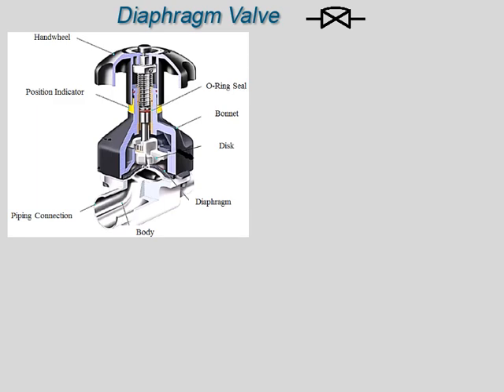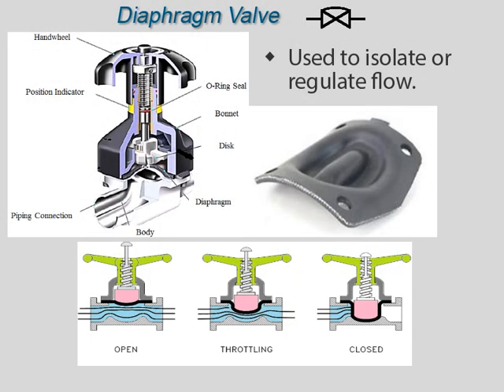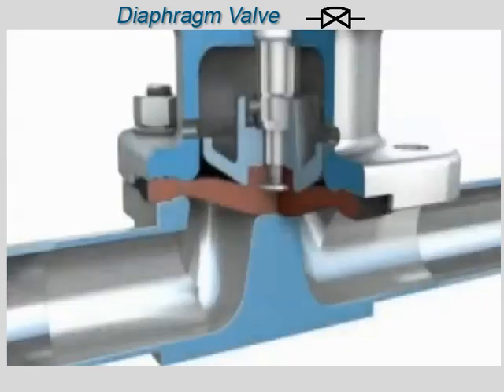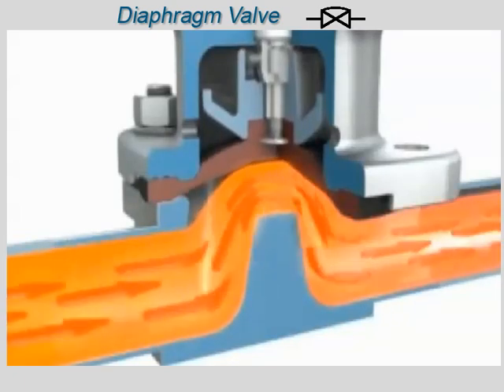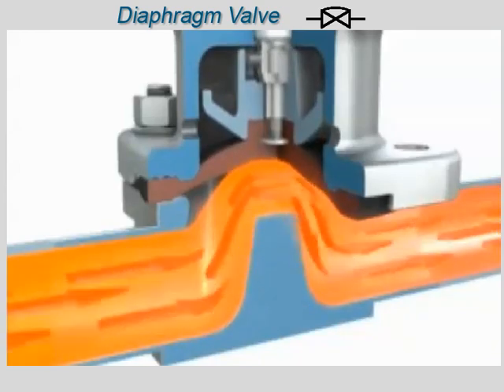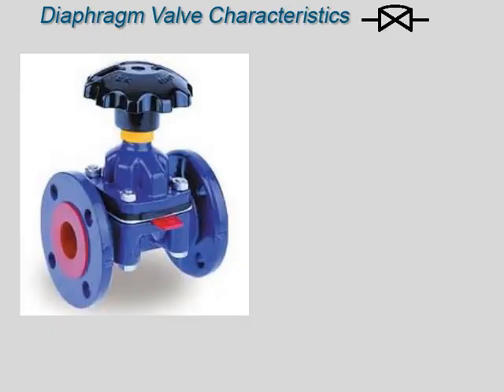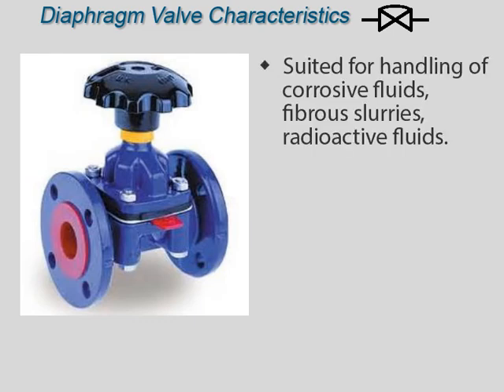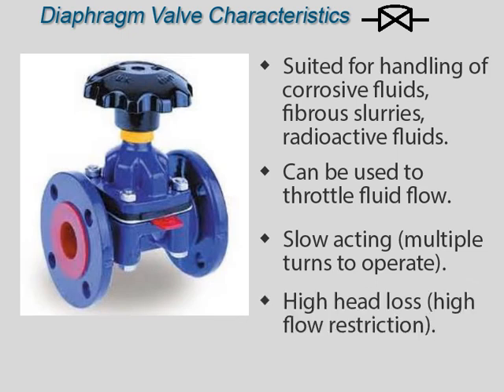A diaphragm valve is a linear motion valve used to isolate or regulate flow. The name is derived from its flexible disc made of rubberized material or thin metal, which mates with a seat located in the open area at the top of the valve body to form a seal. Because the diaphragm isolates the body cavity of the valve from the bonnet, stem, and disc, these types of valves are good for use with dangerous liquids that could be hazardous if they leaked out along the stem. The main advantages are that they are suited for handling corrosive fluids, fibrous slurries, and radioactive fluids, and they can be used to throttle fluid flow. They are slow-acting and have high head loss compared to other valves, and are typically smaller in size.